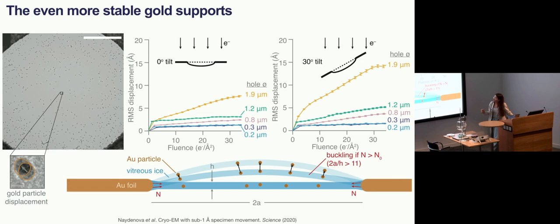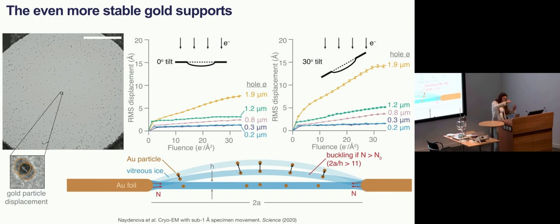To understand remaining motion, we ran experiments looking at how fiducial markers move within the specimen, studying motion as a function of hole size in the support — in both non-tilted and tilted specimens. Tilted specimens show more apparent motion. As hole diameter decreases, the amount of motion also decreases. There is always a big jump in motion at the onset of irradiation, then it levels off. Quite interestingly, when the hole is small enough, the dependence on hole size is completely lost, and the motion becomes the same in non-tilted and tilted specimens — it becomes isotropic.